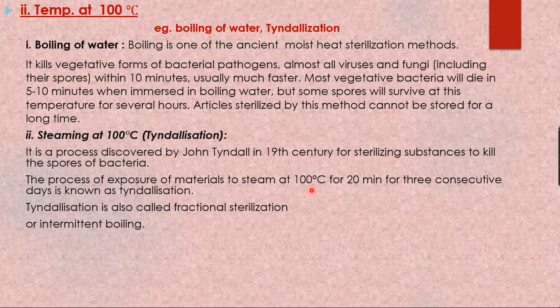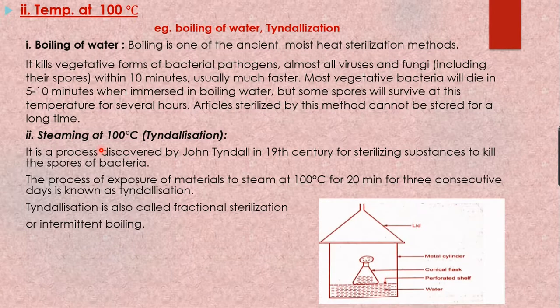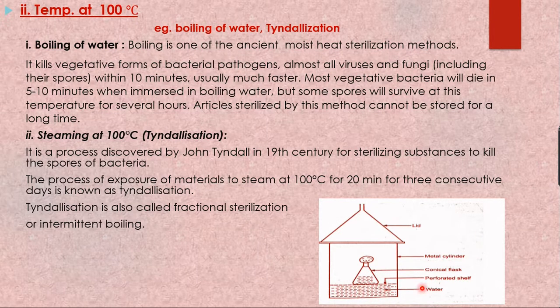Tyndallization is also called fractional sterilization because the sterilization is applied in a fractional manner over three consecutive days, essentially intermittent boiling at 100°C. This is how temperature at 100°C is applied in the sterilization process. The tyndallization equipment consists of a lid, a substance to be sterilized, water, and a perforated shelf inside a metal vessel — heated on each of the three consecutive days.